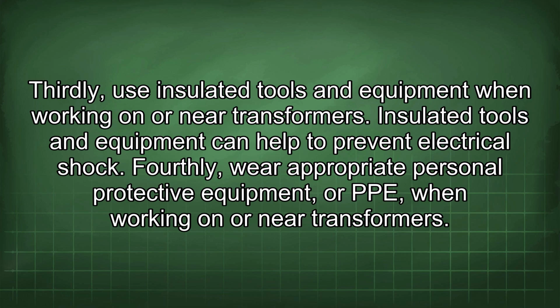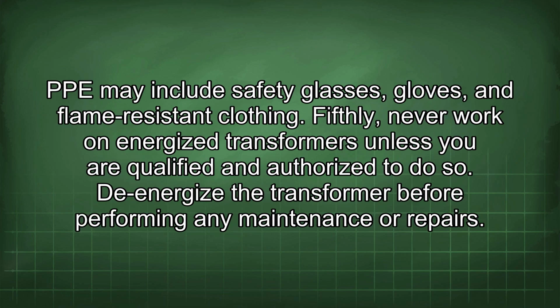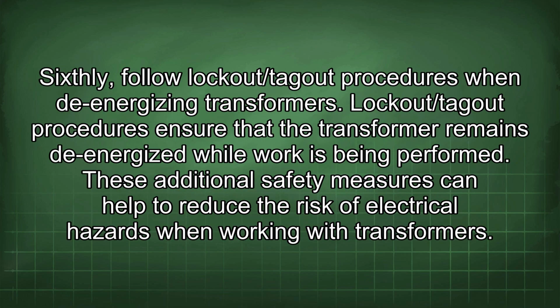Insulated tools and equipment can help to prevent electrical shock. Fourthly, wear appropriate personal protective equipment, or PPE, when working on or near transformers. PPE may include safety glasses, gloves, and flame-resistant clothing. Fifthly, never work on energized transformers unless you are qualified and authorized to do so. De-energize the transformer before performing any maintenance or repairs. Sixthly, follow lockout/tagout procedures when de-energizing transformers.